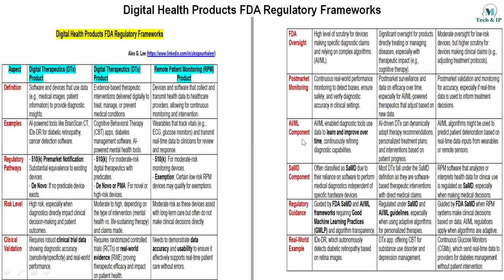But one thing is the AI/ML components. So what do you have? The traditional regulatory pathway is a 510(k), or depending on the risk, whether it's level 1, 2, or 3. Usually level 1 and 2 don't require pre-market approval, but level 3 is high risk, and then you need pre-market approval also. And sometimes it's a new, completely de novo pathway. But among the 910 medical devices, very rarely, only a few are de novo. It's mostly 510(k). So you should think about whether they are SaMD and then AI/ML.